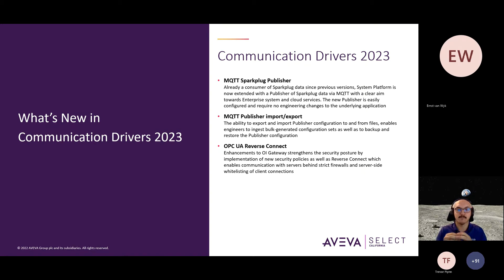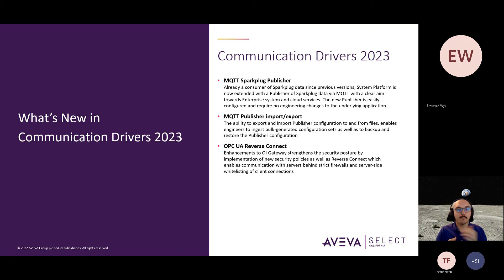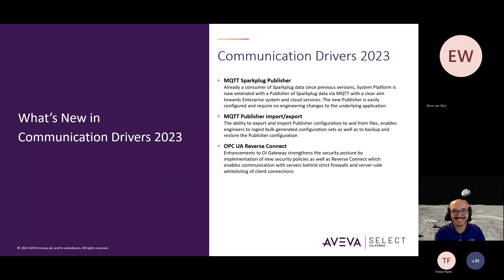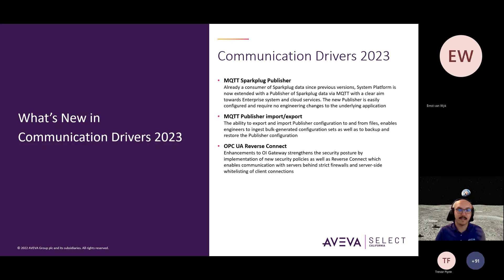One of the things implemented with this new release is the OPC UA reverse connect feature — basically a more secure way of managing connections to different OPC UA clients, in that the OPC UA server is defining and initiating that connection to those respective and designated clients, rather than having any OPC UA client make the connection to the OPC UA server.